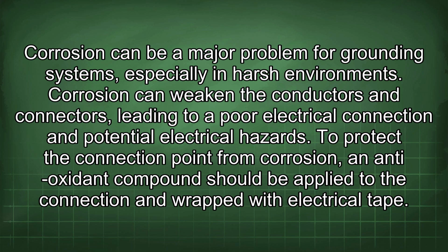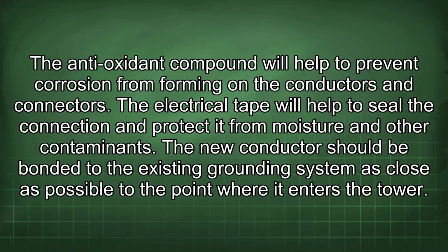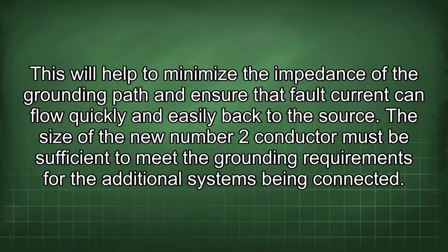To protect the connection point from corrosion, an antioxidant compound should be applied to the connection and wrapped with electrical tape. The antioxidant compound will help to prevent corrosion from forming on the conductors and connectors. The electrical tape will help to seal the connection and protect it from moisture and other contaminants. The new conductor should be bonded to the existing grounding system as close as possible to the point where it enters the tower. This will help to minimize the impedance of the grounding path and ensure that fault current can flow quickly and easily back to the source.